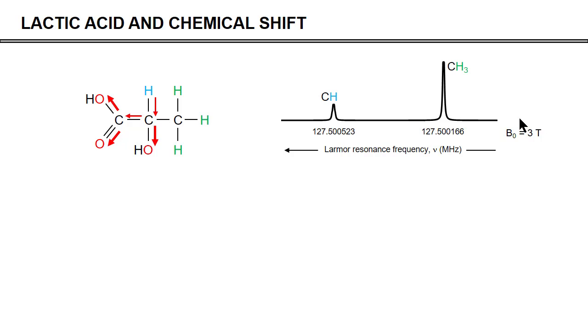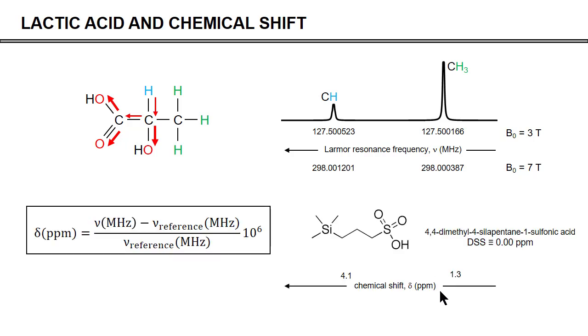At 3 Tesla versus 7 Tesla, the absolute frequencies differ — which is inconvenient if you need to compare with someone using a different magnet. So instead, frequencies are converted to a common chemical shift axis expressed in ppm using a reference compound, DSS, whose nine methyl group protons are defined as resonating at 0 ppm. With this definition and equation, the lactate methyl peak always resonates at 1.3 ppm and the CH proton always resonates at 4.1 ppm — whether measured at 7, 3, or 1 Tesla. This is a very convenient way of creating a uniform axis.